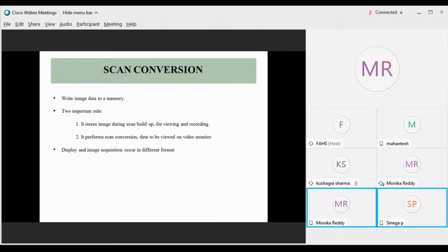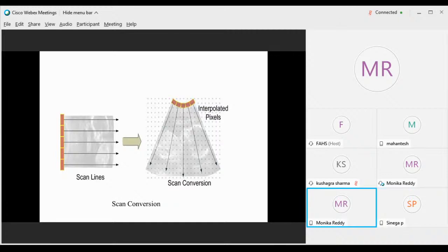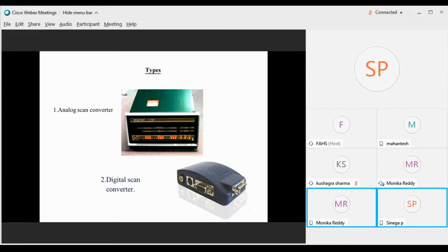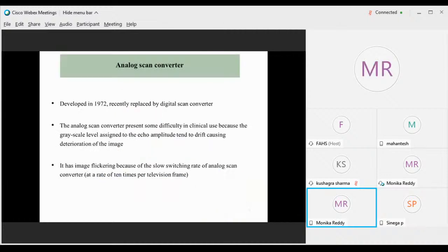So this is how the scan lines, even for the sector, are provided in parallel, but according to the image, it will interpolate into a sectional view for our convenience. There are two types of scan converters, analog and digital. The analog scan converter was developed in 1972, and it is no more, as it has been replaced by the digital scan converter.